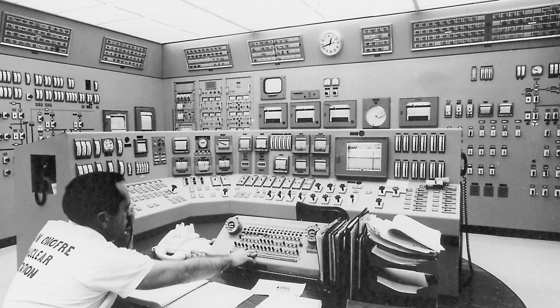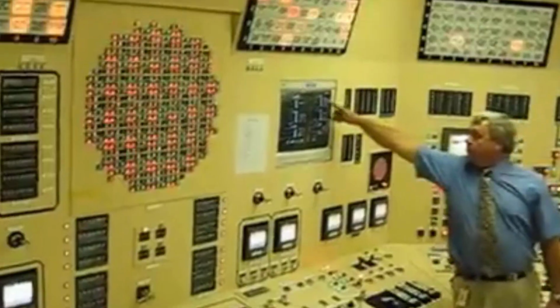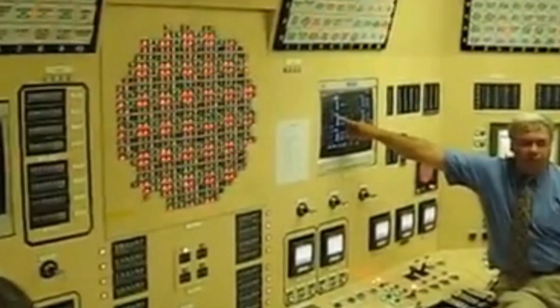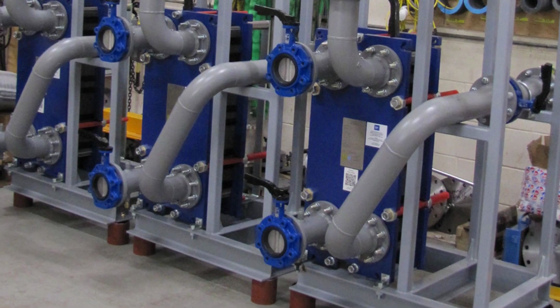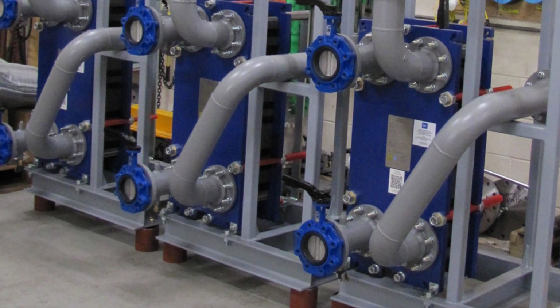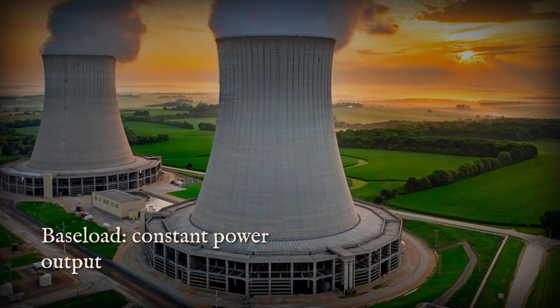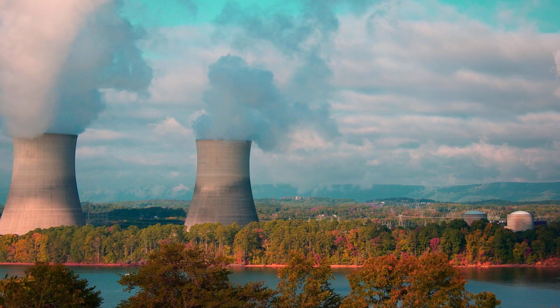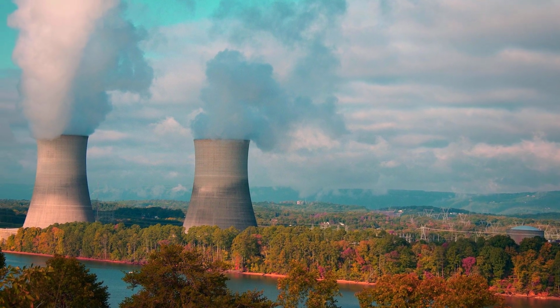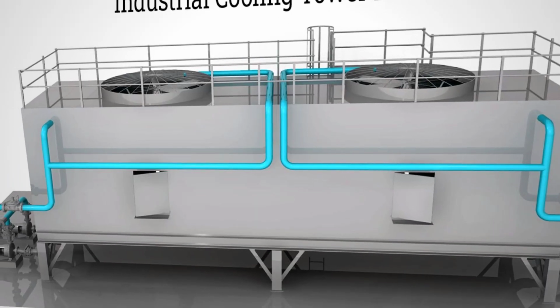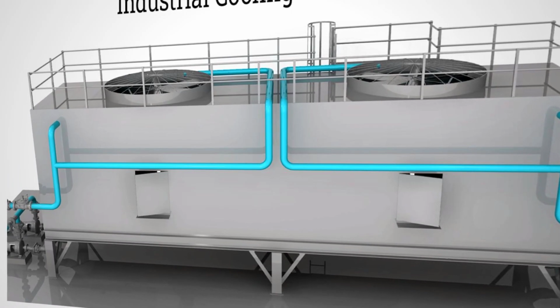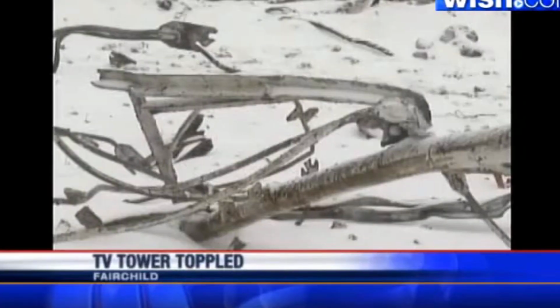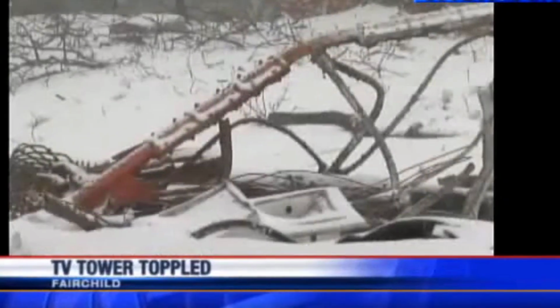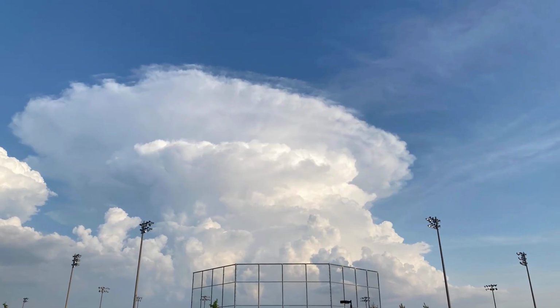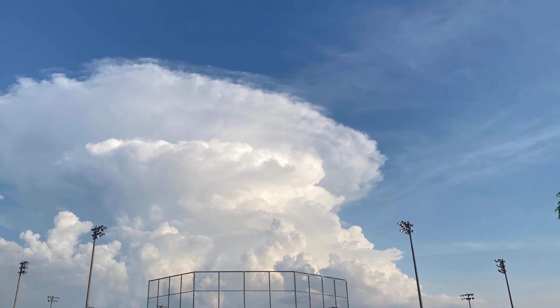They are especially common at nuclear plants for two key reasons. Firstly, reliability is paramount. Cooling is critical for nuclear plant safety, and systems with fewer moving parts, like fans, inherently reduce potential failure points during emergencies. Secondly, they suit the consistent output of baseload nuclear facilities, which typically operate nearly non-stop at a constant power. This allows for a system optimized for a single, steady heat load, unlike mechanical cooling systems that need to ramp up and down. However, even if the heat load remains constant at large baseload plants, the weather changes, and not every climate is ideal for natural draft towers.